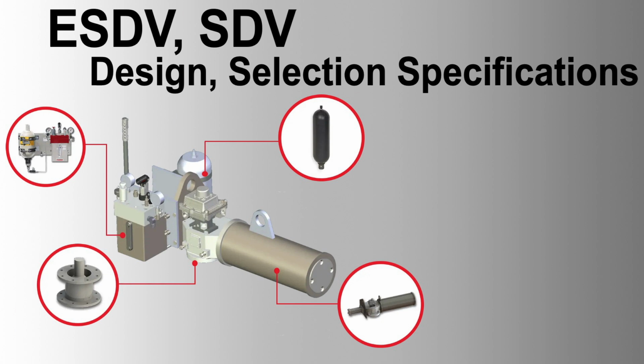NDE requirements. Extent, methods, and acceptance criteria must be specified in the specification for piping valves. Valve seat leakage. Maximum allowable leakage must be specified on the valve data sheets. Leakage class VI per FCI 70-2.